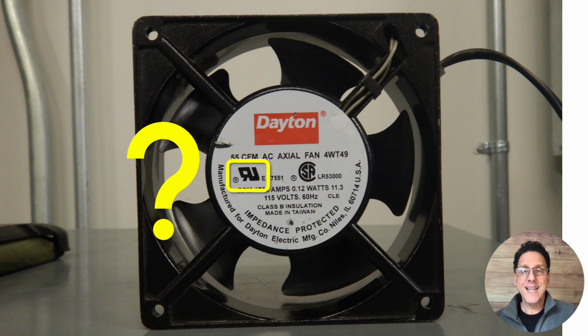A UL recognized component. That indicates that a manufacturer has demonstrated the ability to produce a component for use in an end product that complies with UL requirements. Now, the recognized component mark is applicable to components that are incomplete, if you will, or limited in performance capabilities. These components are generally part of a larger product or system, right? Like the power supply I just showed you in the previous slide, that's part of a bigger cabinet, if you will, a control cabinet with that power supply in it.